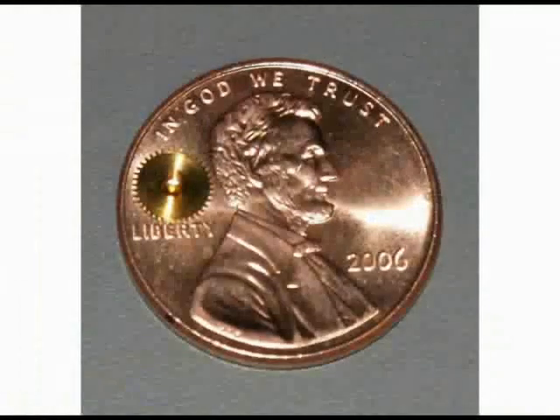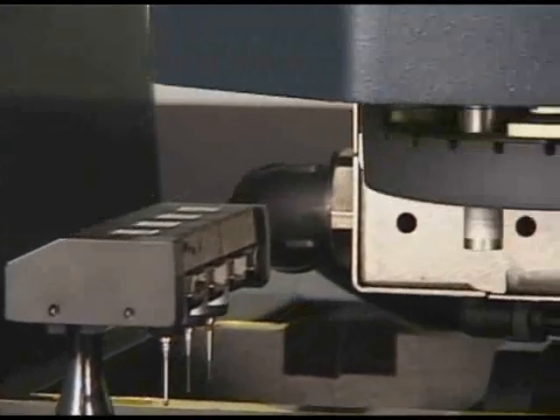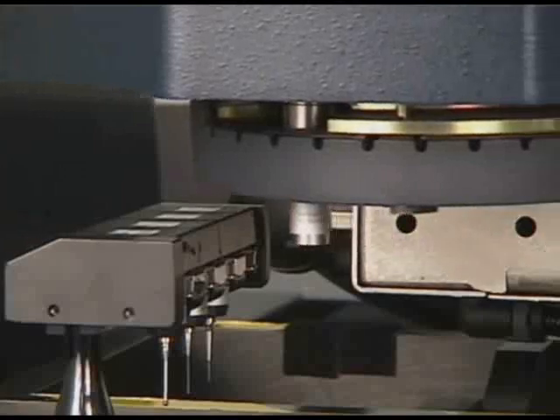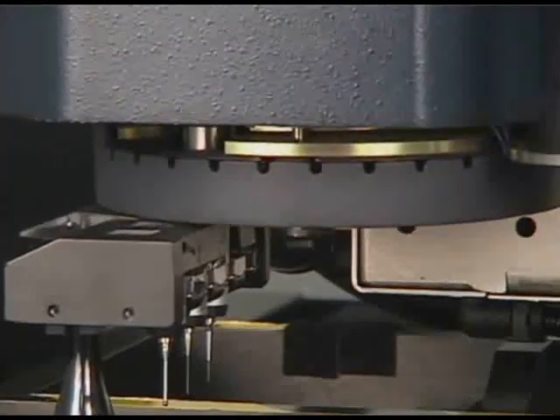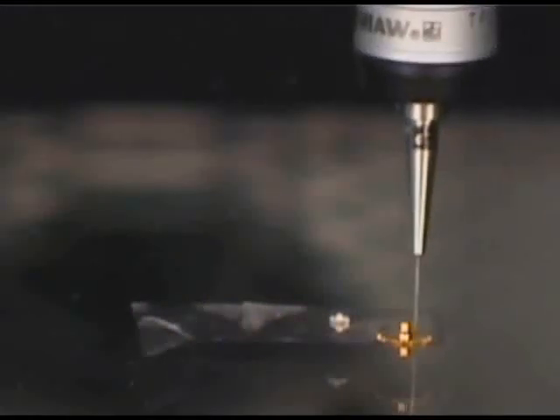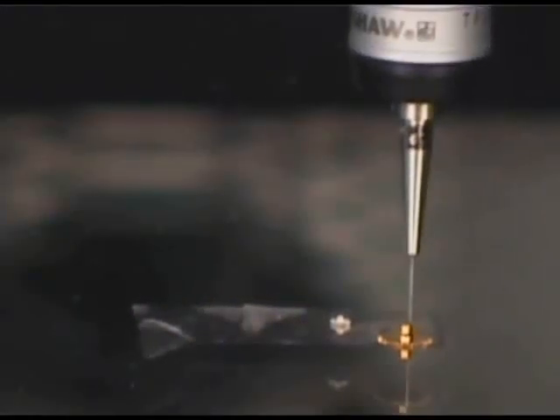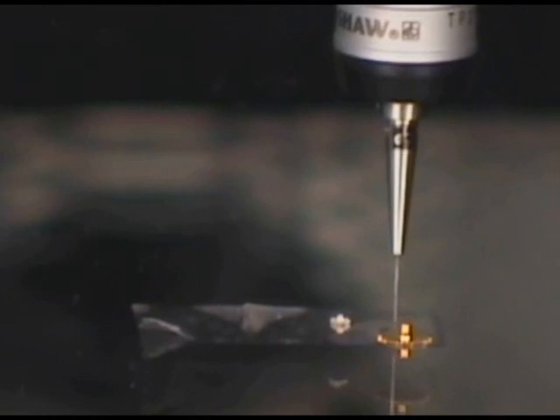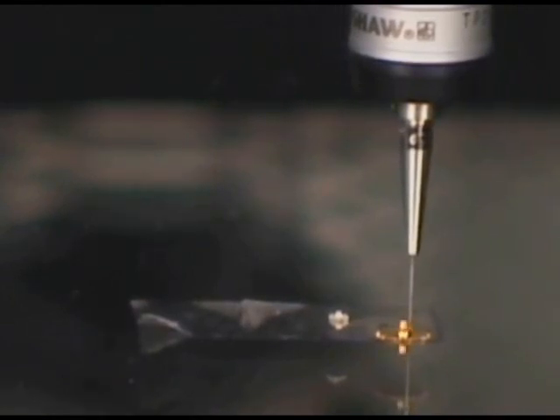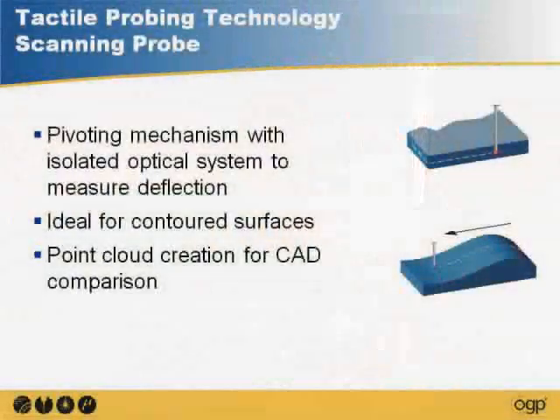Another example is a very small part. You can get down with this conventional kind of probe to about 0.5, 0.3 millimeters, something like that. So this is a very small probe on that small gear mechanism, setting up a datum on that gear. And these probes can be put away and docked and picked up, with different stylus sizes and orientations. So in that respect, they're pretty flexible.